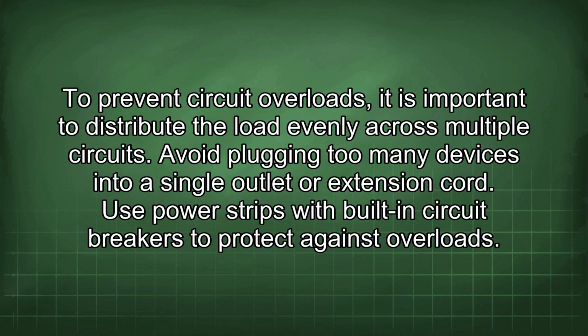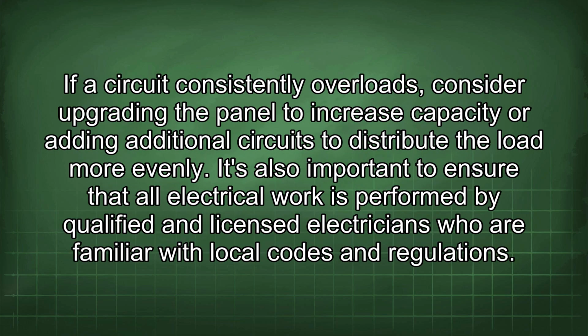To prevent circuit overloads, it is important to distribute the load evenly across multiple circuits. Avoid plugging too many devices into a single outlet or extension cord. Use power strips with built-in circuit breakers to protect against overloads.